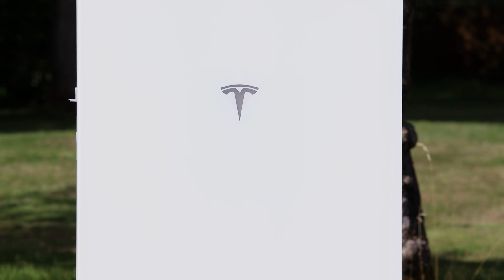If you're getting something like a Powerwall 3, then you might be able to get away with it, as you can set the inverter rating in the software to 3.68 kilowatts, and then your installer can remotely uprate it to a higher setting when the application comes back. But that's not ideal, and the application should really come back before you install anything, as on occasion there are additional charges to connect, and if you've already installed something, then you'll just have to stomach those costs or rip the system out. And no, your installer does not have a special relationship with the DNO, no matter what they tell you.